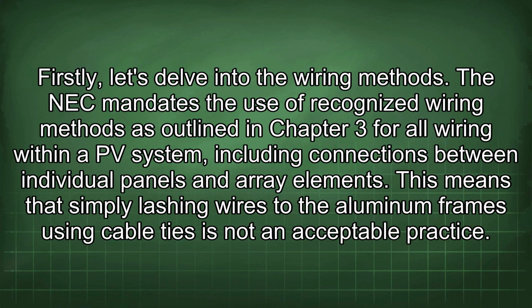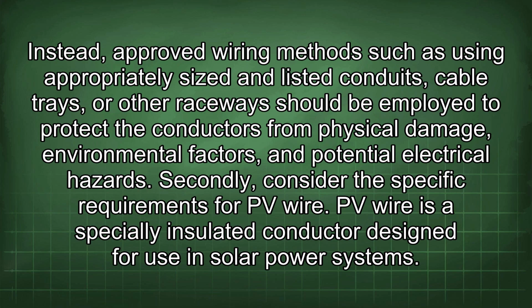Firstly, let's delve into the wiring methods. The NEC mandates the use of recognized wiring methods as outlined in Chapter 3 for all wiring within a PV system, including connections between individual panels and array elements. This means that simply lashing wires to the aluminum frames using cable ties is not an acceptable practice. Instead, approved wiring methods such as using appropriately sized and listed conduits, cable trays, or other raceways should be employed to protect the conductors from physical damage, environmental factors, and potential electrical hazards.